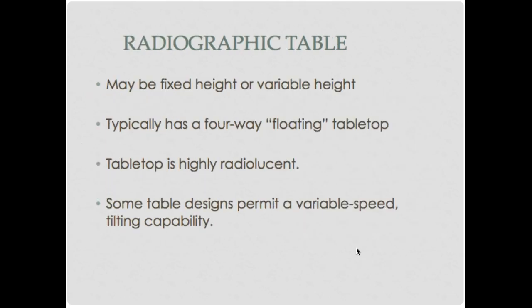The radiographic table may be fixed height or variable height. Some floor tables are not able to adjust down, but basic x-ray tables do raise and lower, which is really nice. We have the floating tabletop, which is a four-way floating tabletop. In fluoro it's usually a fixed-height table with buttons to move the table in four directions. The tabletop is highly radiolucent, usually carbon fiber, and some table designs permit variable-speed tilting, though most now have just one speed.